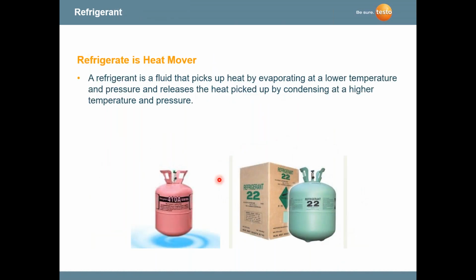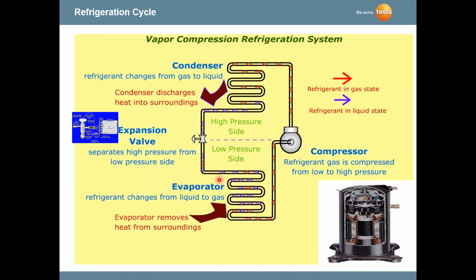So the refrigerant itself is a heat mover. It's moving the heat from an area where we don't want it, which is inside a home or a building, to where it's more acceptable, which would be outside at the condensing unit. So if you look at all these components together, let's take a look. You see the compressor somewhat in the center, and we have red arrows indicating a refrigerant gas state. We have blue arrows that indicate a liquid state. And let's just remember hot to cold, that heat transfer law. Like, you ever hear of follow the money? Well, here you want to follow the heat. So let's start at the compressor.